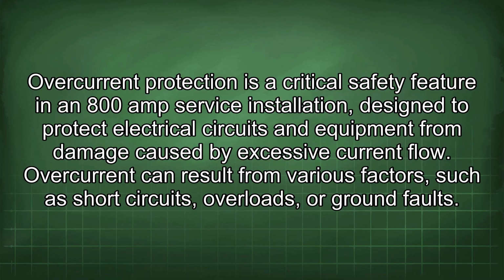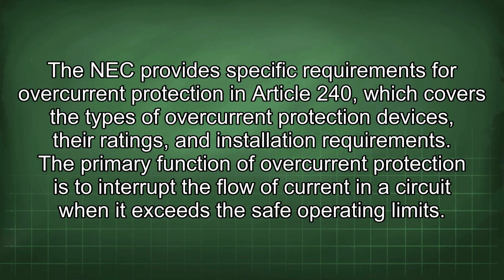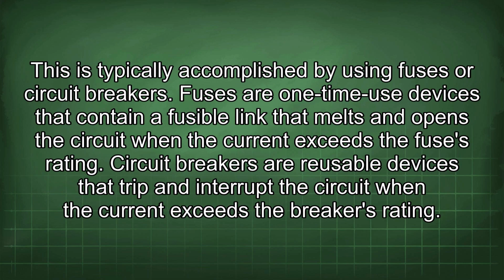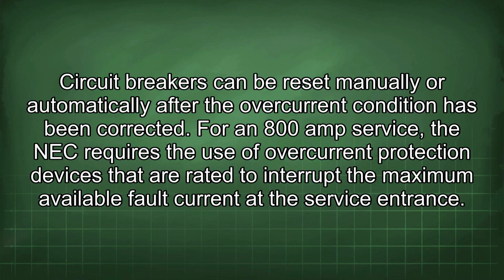Overcurrent can result from various factors such as short circuits, overloads, or ground faults. The NEC provides specific requirements for overcurrent protection in Article 240, which covers the types of overcurrent protection devices, their ratings, and installation requirements. The primary function of overcurrent protection is to interrupt the flow of current in a circuit when it exceeds the safe operating limits. This is typically accomplished by using fuses or circuit breakers. Fuses are one-time use devices that contain a fusible link that melts and opens the circuit when the current exceeds the fuse's rating. Circuit breakers are reusable devices that trip and interrupt the circuit when the current exceeds the breaker's rating. Circuit breakers can be reset manually or automatically after the overcurrent condition has been corrected.